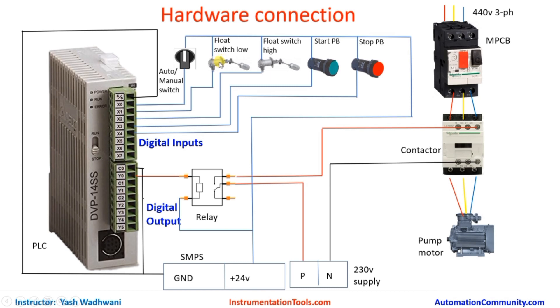Similarly, we take the 24V supply and connect it to the common of the high level float switch, and its NO terminal we connect to the X2 terminal of the digital inputs.